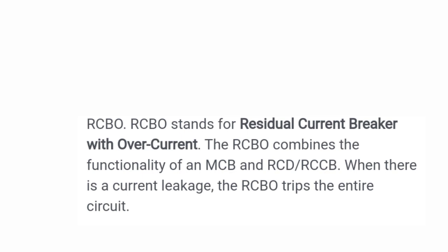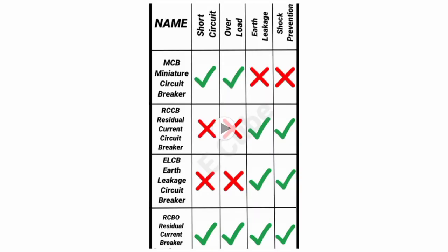Now we can look at the differences. MCB is a miniature circuit breaker — it handles short circuit and overload protection, but has no earth leakage protection. The ELCB is voltage-based and the RCCB is current-based — these are two key differences. The RCBO is the advanced version combining RCCB and MCB, providing both overcurrent protection and residual current protection, covering short circuit and overload.